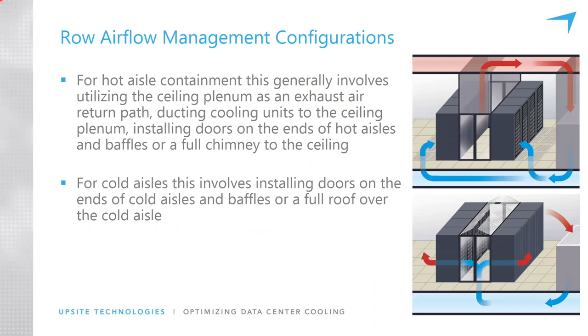So here's the basic configurations of either having a hot or a cold aisle. You can see quite clearly in this picture, we're doing hot aisle containment. So we're containing all the exhaust air that's going into the hot aisle and channeling it back to the cooling units. That means all the air that comes out into the room, this rest of the space, is a cold space, and the designated contained space is the hot space. And vice versa, cold aisle containment looks like containing the space where the cold air is delivered to the face, the fronts of the cabinets, and then the exhaust air just flows out into the room. So that's the hot aisle.